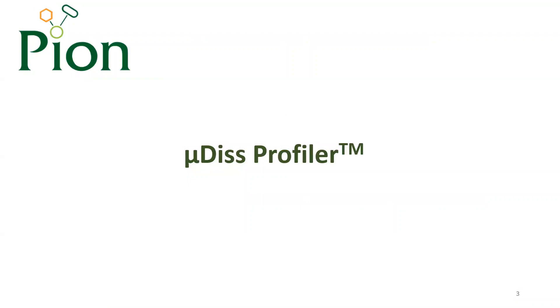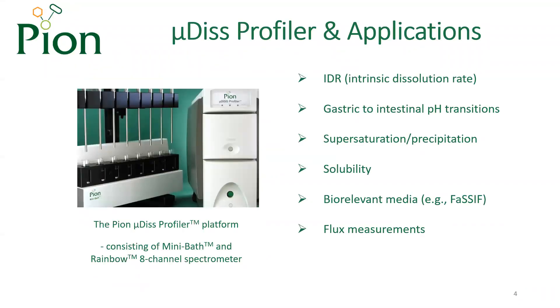Let's make a start with a look at the µDiss Profiler, the platform we have used for studying nanoparticulate systems. The µDiss Profiler is an eight-channel small-scale dissolution platform that consists of the mini bath and rainbow spectrometer. The mini bath is used for magnetic stirring and temperature control. The rainbow spectrometer consists of a deuterium light source connected to eight fibre optic UV probes and eight individual spectrometers. The fibre optic probes are introduced into µDiss Profiler vessels and can be used to determine concentrations of drug substance during experiments by using UV spectroscopy.